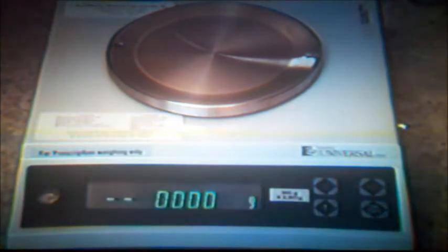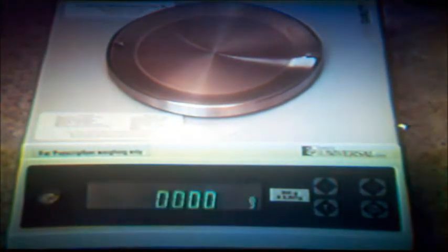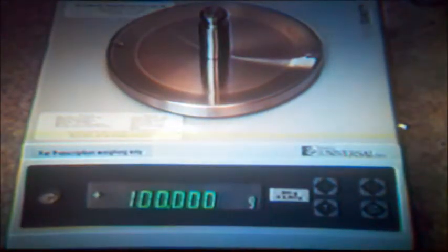The display will scroll through its menu, indicating node T/C, node G, and then cal. At this point, let go of the T button and remove the calibration key. The display will start flashing 0.000 G. This will be followed by a flashing 100 G display. Place the 100 G weight on the pan and watch until the display becomes static, reading 100.000 G.